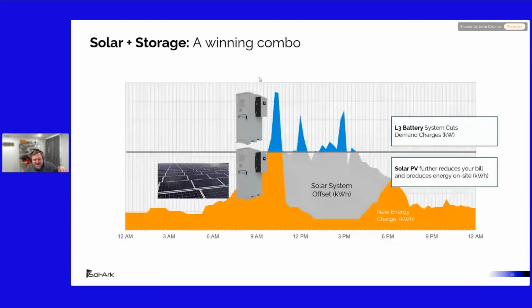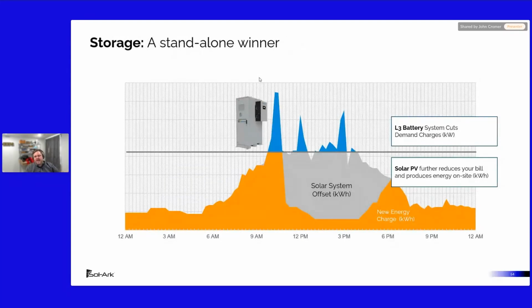By the time you look at the building demand profile and want to do building backup—with one inverter and one battery cabinet—find anything small on site that needs backup: a refrigerator system, building lights, or a computer system. Say, when the power goes out, you want to keep these things powered so you can enter and exit the property well, or keep bare business functionality operating and avoid revenue loss. Instead of doing whole building backup, doing it with just a subdivision keeps the economics very good.